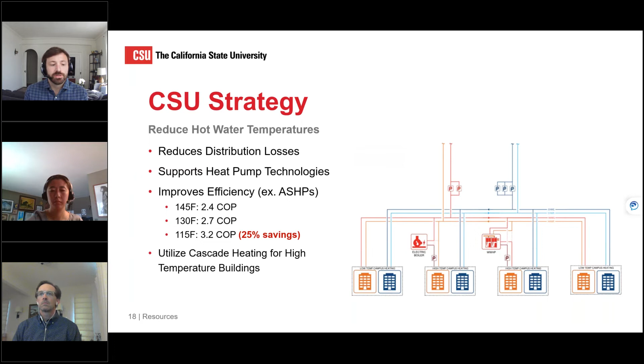So there's a significant efficiency benefit. And also looking at strategies around cascade heating for higher temperature buildings. There are buildings at CSU that will require higher hot water temperatures just due to the existing infrastructure. But we don't want an individual building to prevent the overall campus from reducing hot water temperatures and supporting the overall loop. So we can look at additional heating, whether it's an electric boiler or a water-to-water heat pump that can boost hot water temperatures at individual buildings. CSU campuses have been very successful at resetting their temperatures. For example, Dominguez Hills' hot water system was originally designed at over 200 degrees. They now operate at 160 to 170 in the winter and down to 130 in the summer. So I think it's been shown that we have the ability to reduce hot water temperatures within the existing infrastructure. And I think it really comes down to finding a process for testing at individual buildings and at the overall campus to support heat pump technologies in that long-term transition.